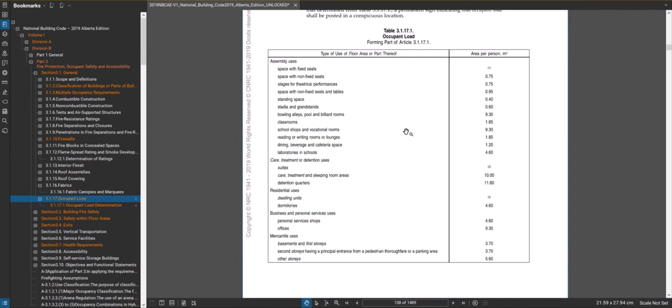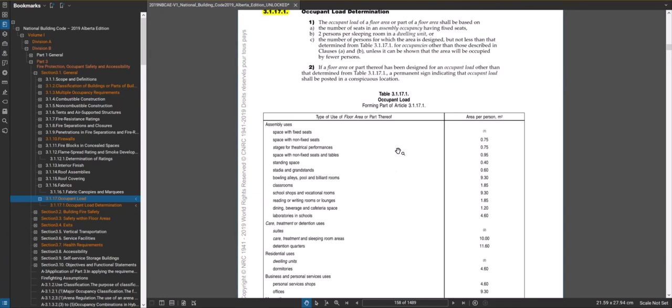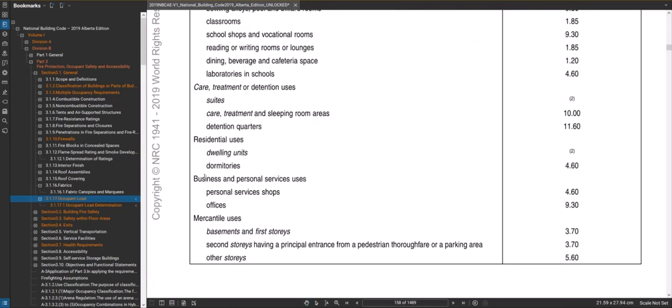In most instances all you do is — take an office for example — figure out your office area and divide it by 9.3, and that's how many people you have. If you have a 200 square metre office, divide 200 by 9.3 and you get 21.5 people. You can't have 0.5 of a person, so you round up to 22. With that number you can figure out the required egress door width from that suite.